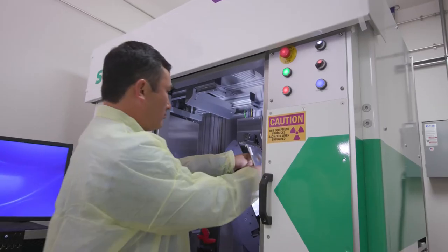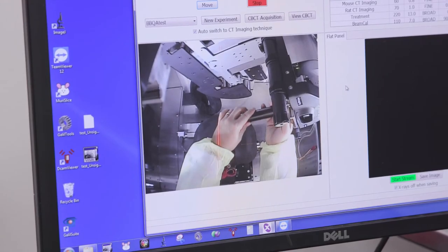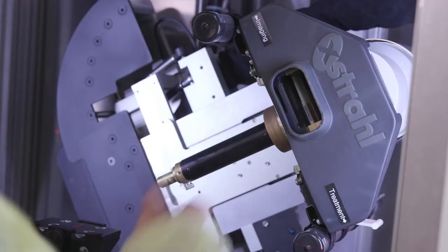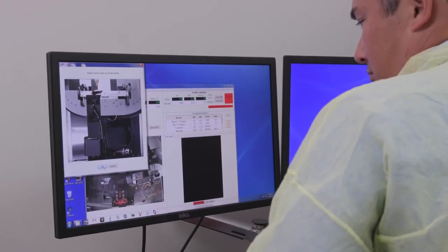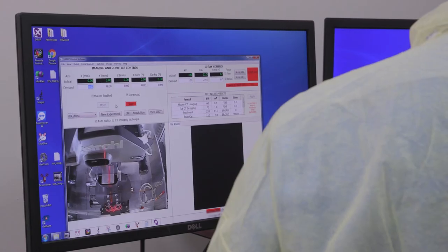In the discussions leading up to getting the new irradiator system, we were proactive in making sure we brought all the users of the system together to discuss the change, to address their concerns, and made available to them the opportunity to do tests between the cesium source and the x-ray source to make sure that the results they were getting were consistent between the old source and the new source. We worked with them to do pilot testing to make sure that whatever effect they were looking at was equal between the two groups, or between the two treatment approaches, and overall we were able to bring everybody on board in the end.